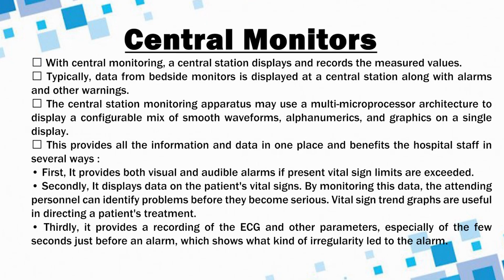Now coming to the concepts of central station monitoring. With central monitoring, a central station displays and records the measured values. Typically, data from bedside monitors is displayed at a central station along with alarms and other warnings.